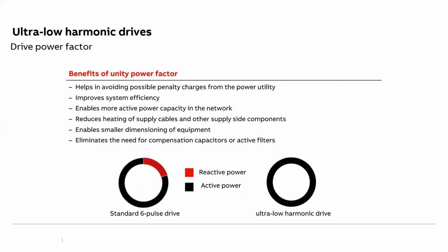Now, whatever disadvantages we had seen of the passive filter, active filter, and other mitigation techniques, all those disadvantages are now taken care of in the ultra low harmonic drive or the active front end technology. So here there is no power factor issue. In fact, this improves the overall power factor. With active front end technology, we can achieve a power factor of unity, pure one. So this can in fact help to improve the overall power quality.